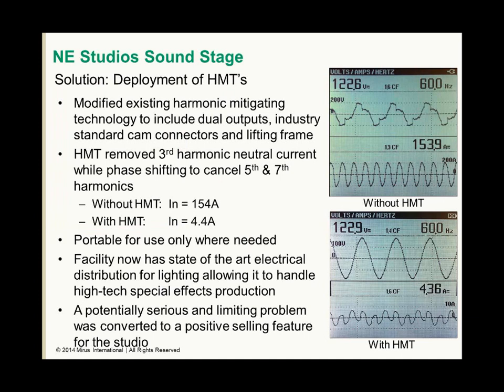The HMT removed third harmonic current while phase shifting to cancel fifth and seventh harmonics. Neutral current without the HMT was 154 amps, and with it was only 4.4 amps. Improvement in voltage distortion was also very evident. The facility now has state-of-the-art electrical distribution lighting, allowing it to handle these high-tech special effects productions.